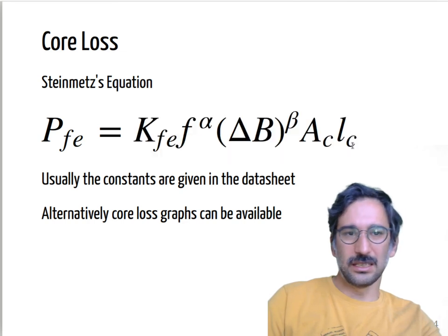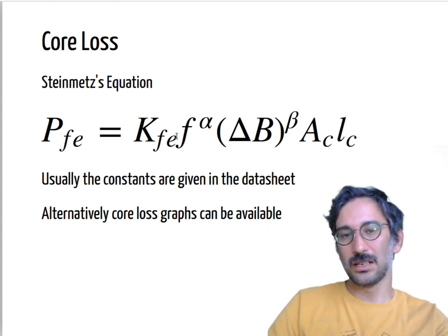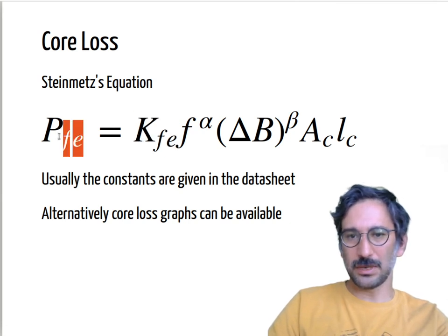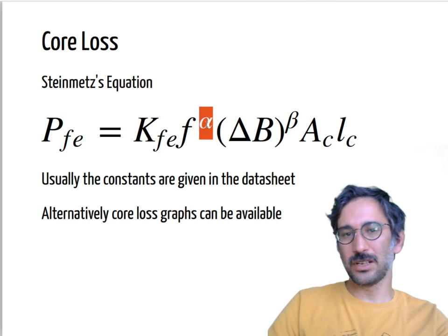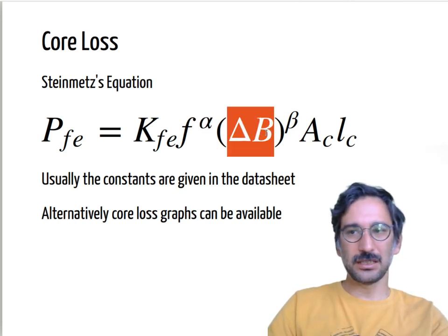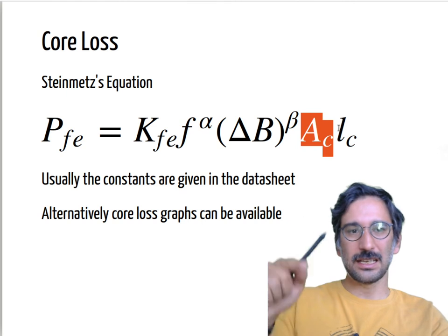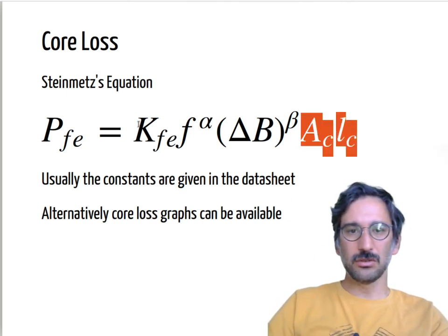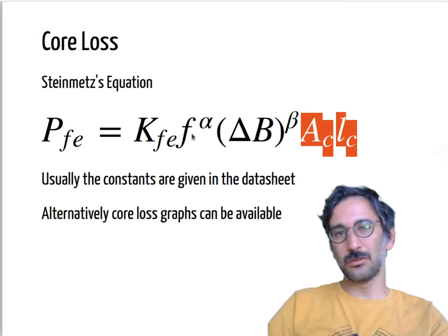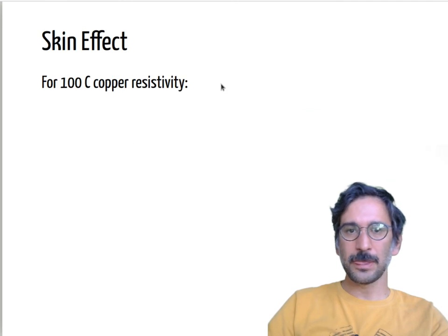When data sheet values don't cover your exact operating frequency, the Steinmetz equation is used: P = k · f^α · B^β · A_c · l_c, where k, α, and β are material constants found in the data sheet or references, f is switching frequency, B is operating flux density, and A_c · l_c is essentially the core volume. Once you know those constants, your switching frequency, and your flux density, you can calculate all core losses.